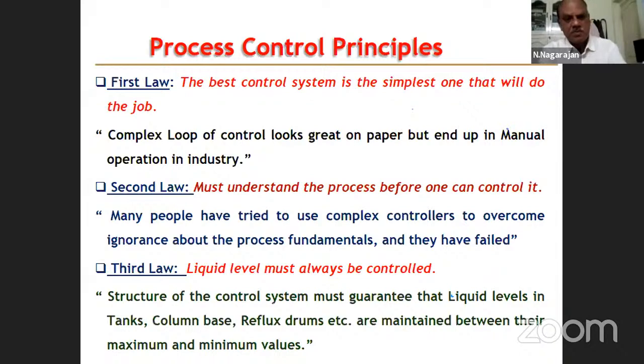So a complex loop of control looks great on paper, but ends up in manual operation in industry. So it may look very beautiful in the paper and the drawing, but when they set up the plant and they start running the plant, operators may have problems. Sometimes the variables will not be cooperating. Maybe there will be hunting between two variables. That is called hunting. So when you control the level, the flow may go out of control. When you control the flow, level may go out of control. This kind of thing may happen if the control loop is not properly designed.